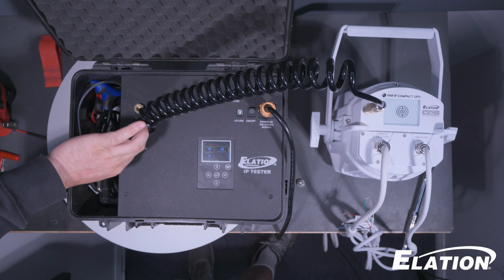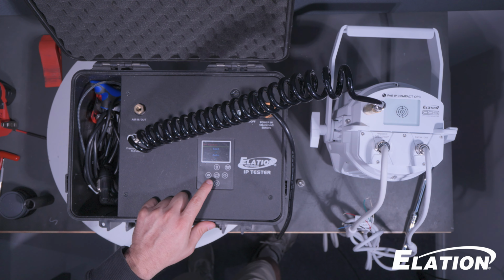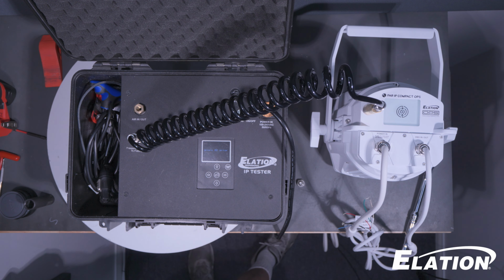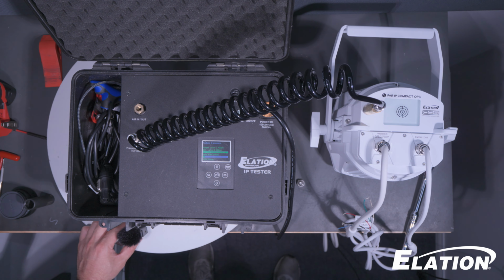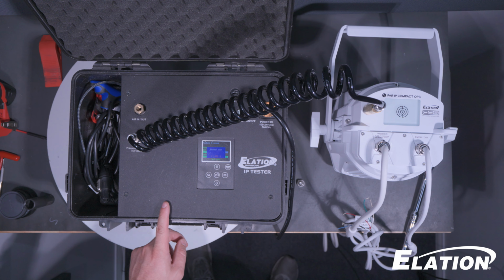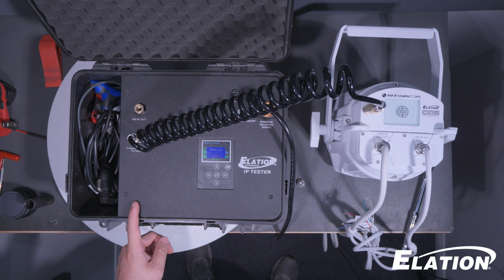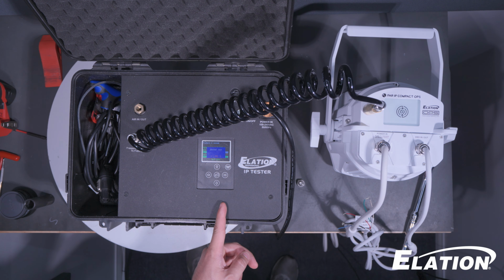And then I'm going to let all the air back in that was pulled out from the unit when I was vacuuming. Put that back in. Test, auto, fixture A. Go ahead and run the test again. So you saw the bar that was loading up all the way, and then it drastically dropped down a lot. That doesn't really matter. The whole goal in this is that when it does take that drop down, that it doesn't go any further down than that. So you want it to stay there. Even if it goes a little bit further down, but it kind of settles in, then that's completely fine too. That's what we're really looking for.